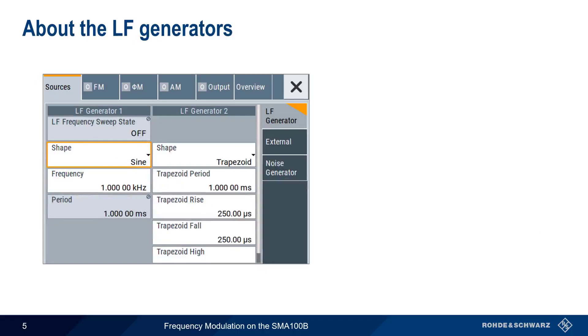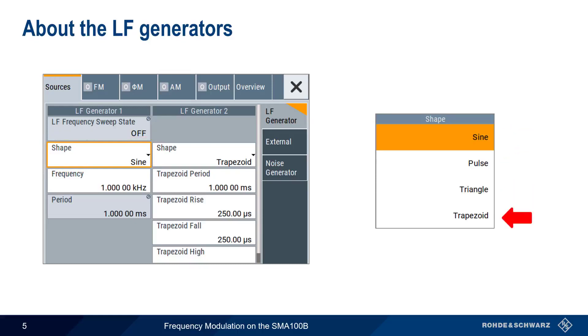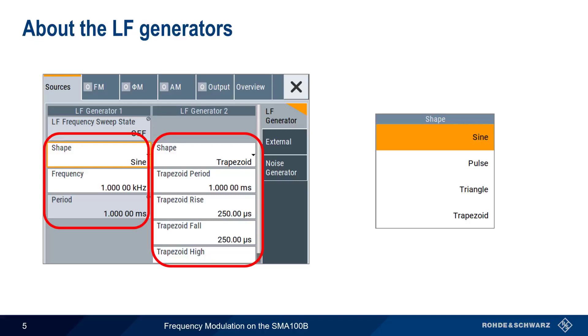The SMA contains two internal LF, or low-frequency generators. You can think of these as simple function generators that are built into the instrument, and which can be used as modulation sources. Each LF generator supports four different shapes: sine, pulse, triangle, and trapezoid. The configuration parameters will be different depending on which shape is chosen.